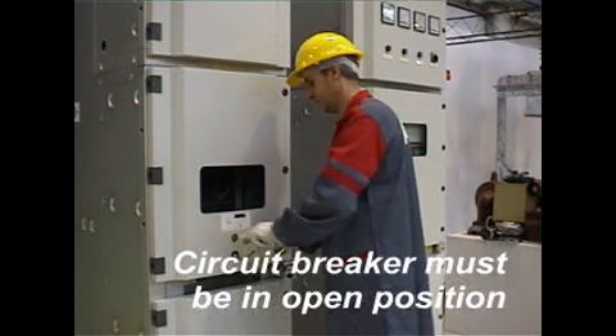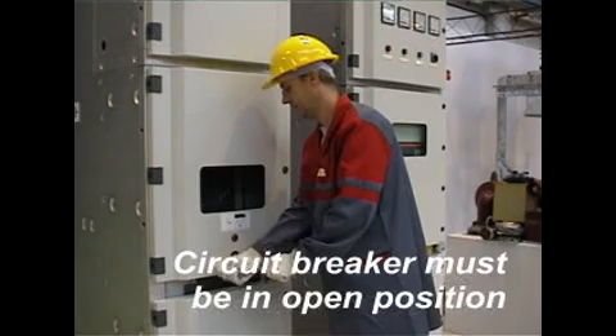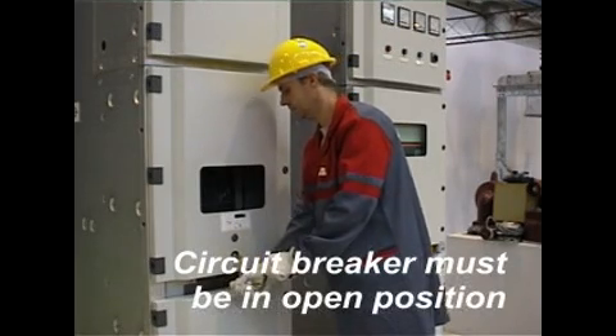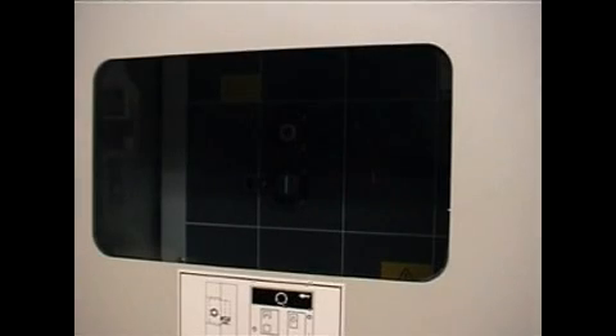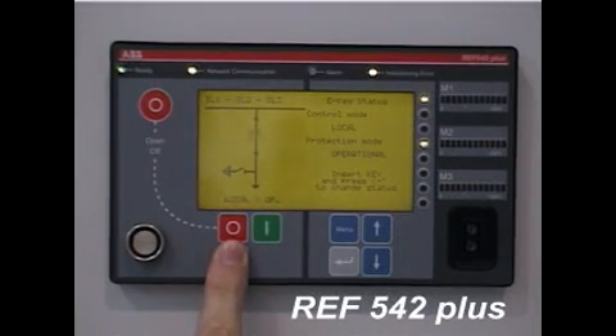The operator cannot withdraw the breaker. In fact, if you give a closer look through the window, we can see that the circuit breaker is inserted but in closed position, therefore we need to trip it by means of the REF542+. The screen of the REF542+ now shows that the circuit breaker is inserted and open, as confirmed by this quick view through the door.